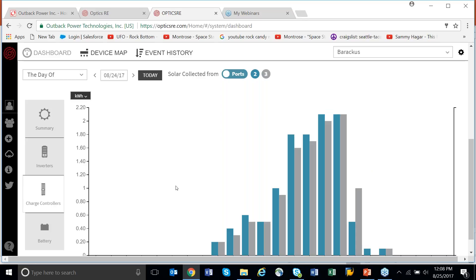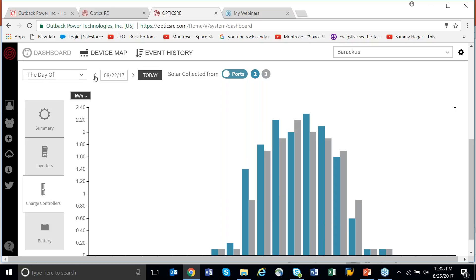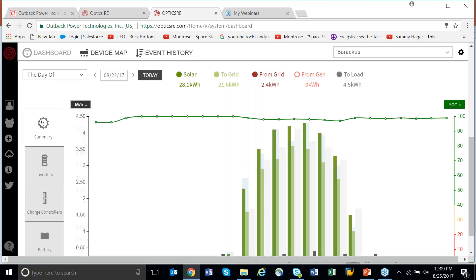This is nice because if you're watching this and you say three days ago I suddenly lost part of an array or an entire charge controller, you can go back and say it worked up to this day and this time. Is there anything that happened during that day? Call up the customer and say yeah, we had some guys up cleaning the roof — maybe they kicked a wire, maybe they unplugged just one string of modules. The advantage of Optics is you as an installer can view your customer's site from virtually anywhere in the world. I've monitored my system from Africa and can even start a generator remotely.